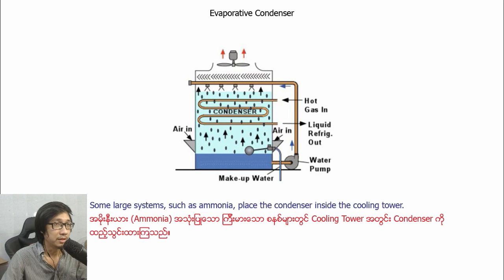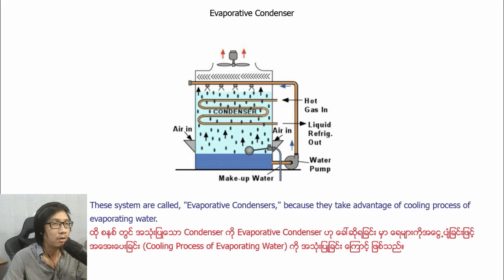Evaporative condenser. Some large systems such as ammonia place the condenser inside the cooling tower. These systems are called evaporative condensers because they take advantage of the cooling process of evaporating water.